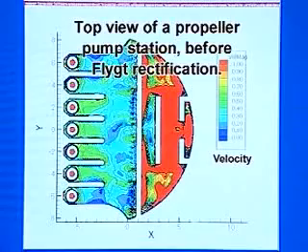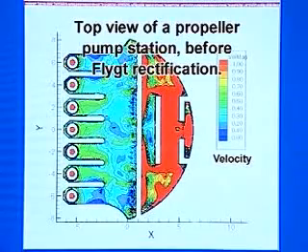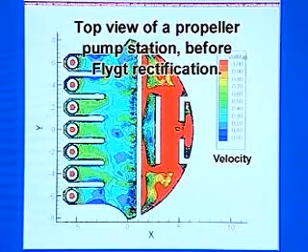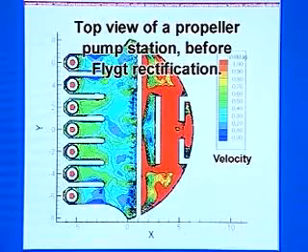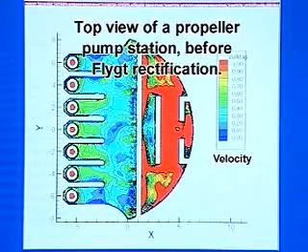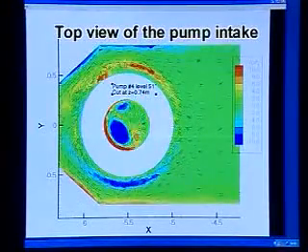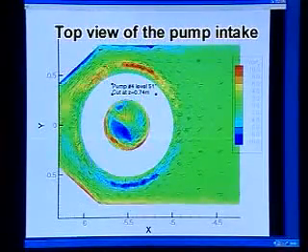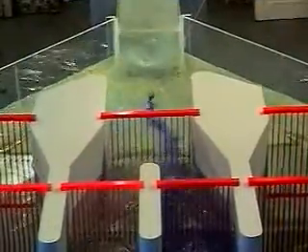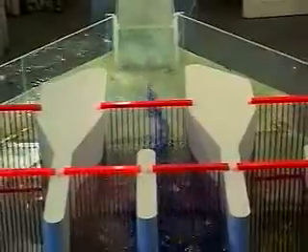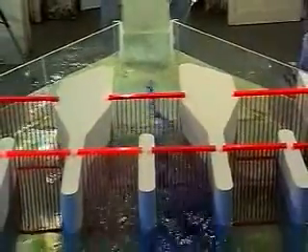Lack of uniformity can cause the impeller to operate away from the optimum design condition and therefore at a lower hydraulic efficiency. Unsteady flow causes the load on the impeller to fluctuate, which can lead to noise, vibration and bearing problems. Swirl in the pump intake can cause significant change in the operating conditions for the pump and can produce changes in the flow capacity, power requirements and efficiency.